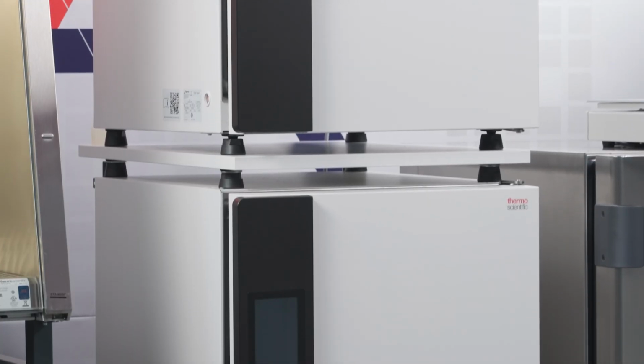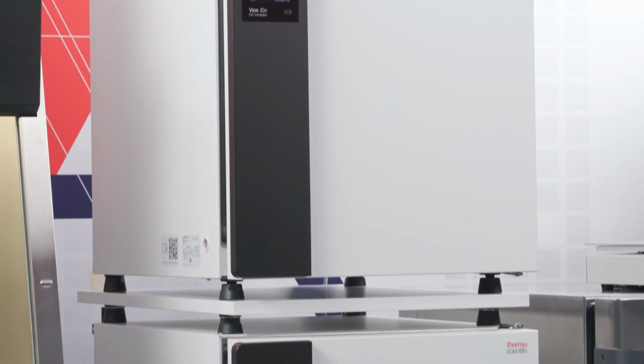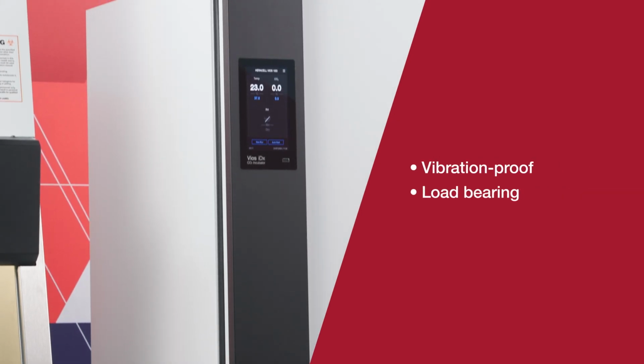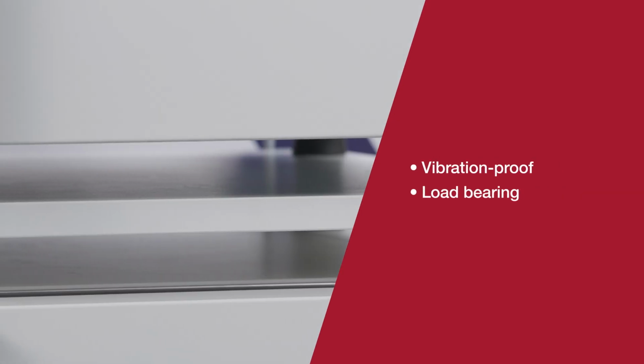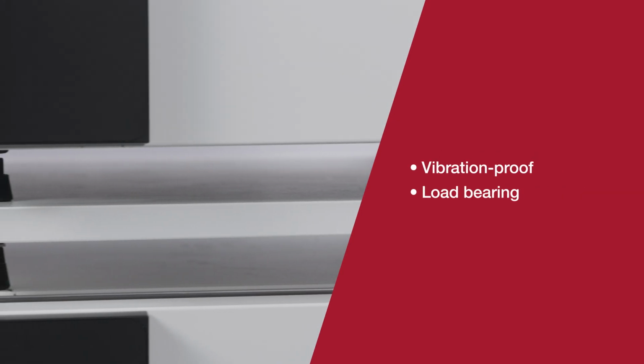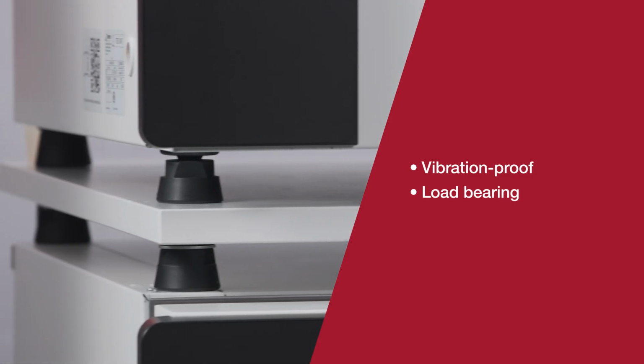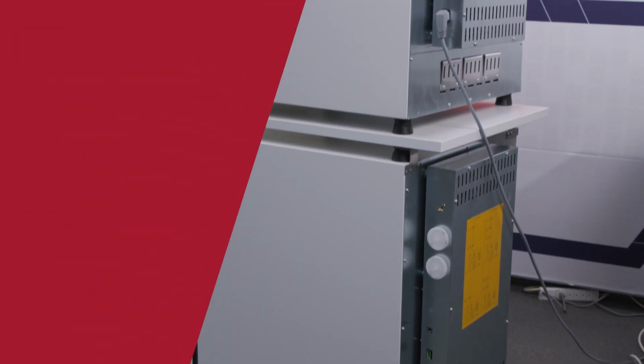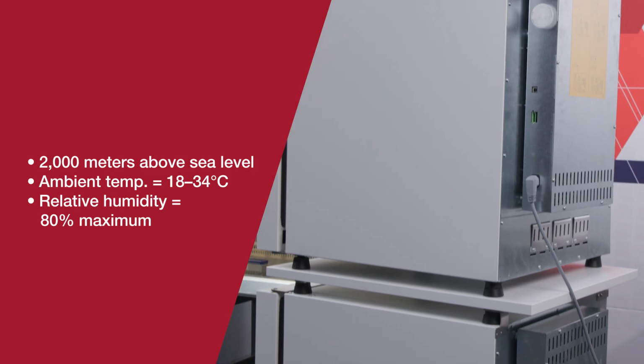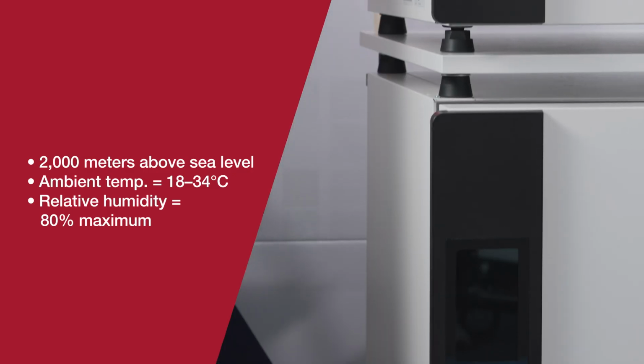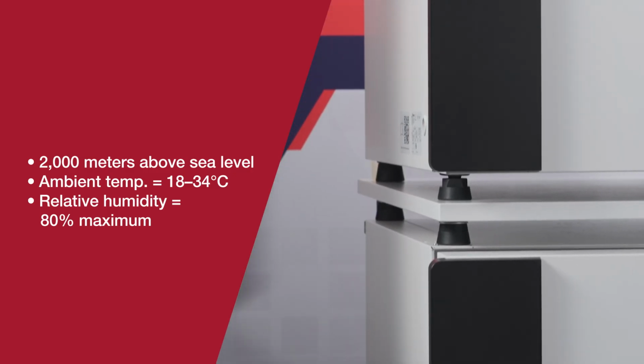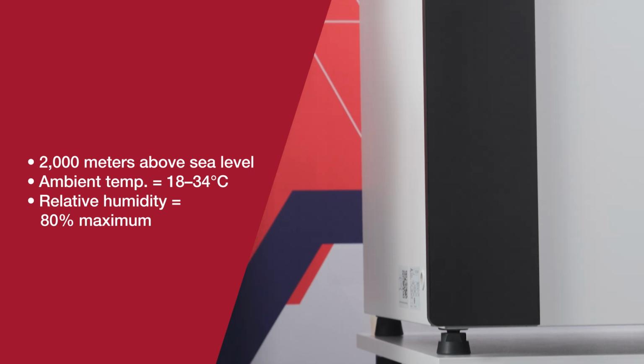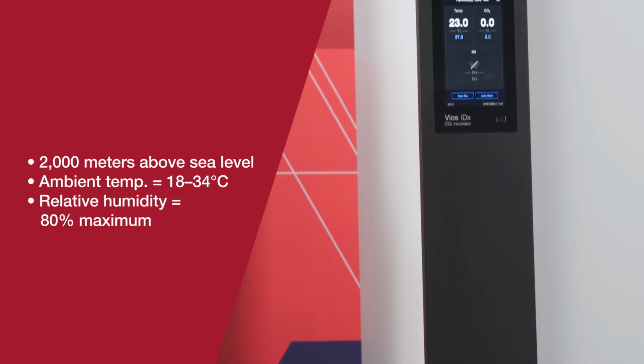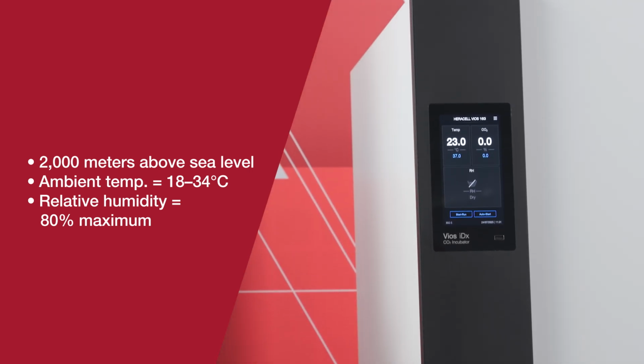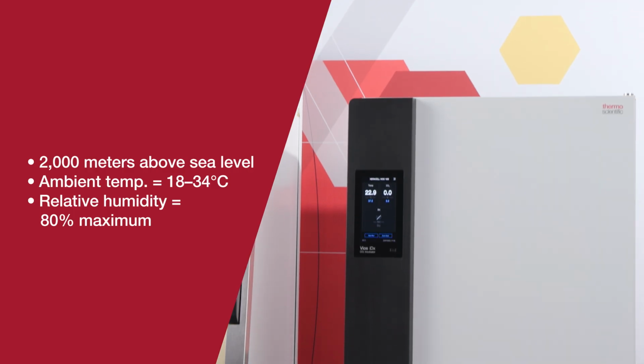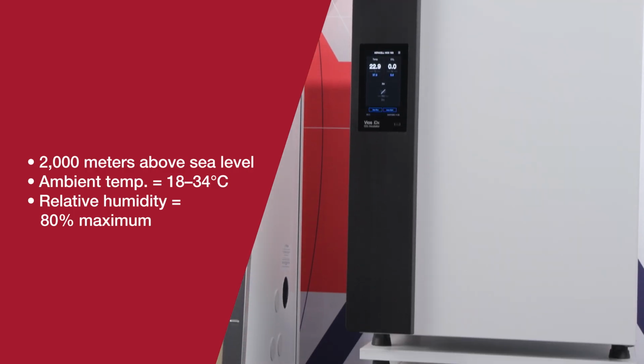If you place your incubator on a floor stand or lab table, the substructure must be vibration-proof and capable of bearing the weight of the device and its accessories, especially if devices are stacked. The electrical system of the device is designed for an operating height of up to 2,000 meters above sea level. To help ensure a constant incubation temperature of 37 degrees Celsius, the ambient temperature must be within a range of 18 to 34 degrees Celsius. The relative humidity of the location shouldn't exceed 80%.